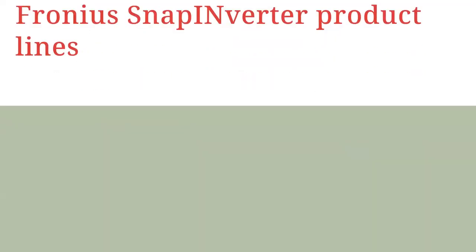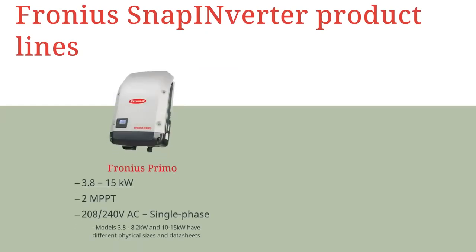Our flagship residential inverter is the Fronius Primo. The Primo is our single-phase inverter ranging from 3.8 kW to 15 kW, perfect for small to large residences. The Primo features two maximum power point trackers and can be integrated into a single phase of a 208-volt grid or on a split-phase 240-volt grid. There are two variants of the Primo with different physical size and design parameters, so be sure to use the correct data sheet.